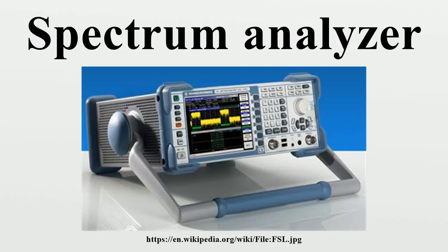Types. Spectrum analyzer types are dictated by the methods used to obtain the spectrum of a signal. There are swept-tuned and FFT-based spectrum analyzers. A swept-tuned spectrum analyzer uses a superheterodyne receiver to down-convert a portion of the input signal spectrum to the center frequency of a band-pass filter. With a superheterodyne architecture, the voltage-controlled oscillator is swept through a range of frequencies, enabling the consideration of the full frequency range of the instrument.